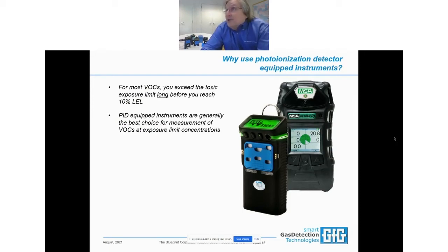One of my favorite and most highly respected competitor products out there would be the MSA 5X. This is the actual difference in size between the 999 and the 5X. And the MultiRAE Pro, the ISC MX6 hybrid, these are all about the same size as well. So you'll notice that the MSA 5X does not have a slide for the pump. The pump operates all the time. 100% of the time you're pulling power out of that 5X internal battery pack.